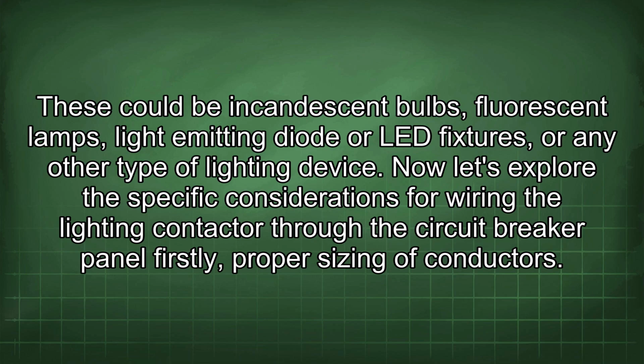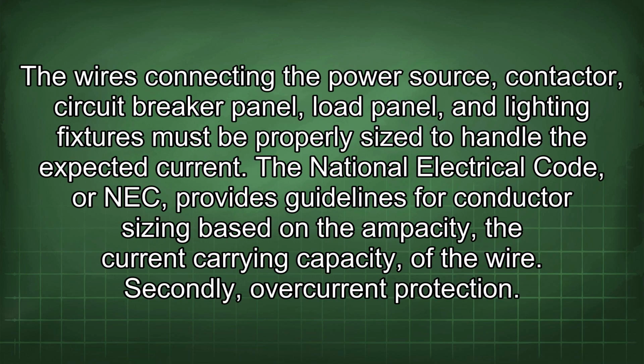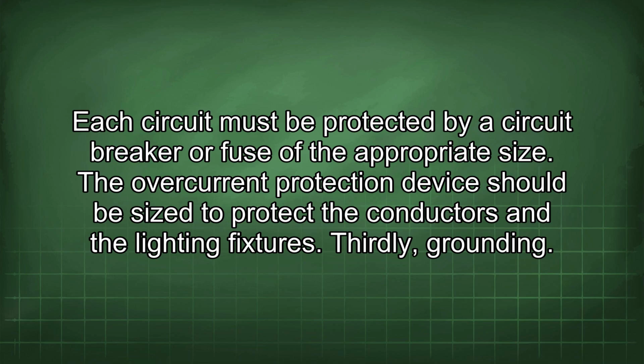Now let's explore the specific considerations for wiring the lighting contactor through the circuit breaker panel. Firstly, proper sizing of conductors. The wires connecting the power source, contactor, circuit breaker panel, load panel, and lighting fixtures must be properly sized to handle the expected current. The National Electrical Code, or NEC, provides guidelines for conductor sizing based on the ampacity, the current carrying capacity, of the wire. Secondly, overcurrent protection. Each circuit must be protected by a circuit breaker or fuse of the appropriate size. The overcurrent protection device should be sized to protect the conductors and the lighting fixtures.